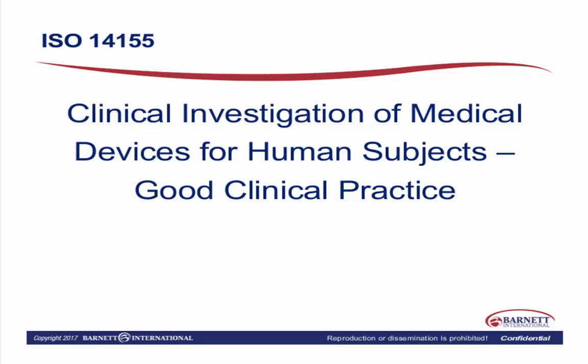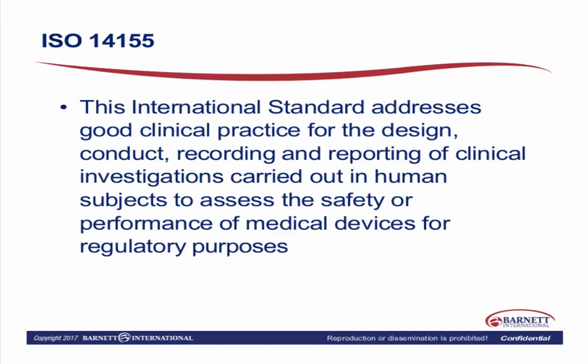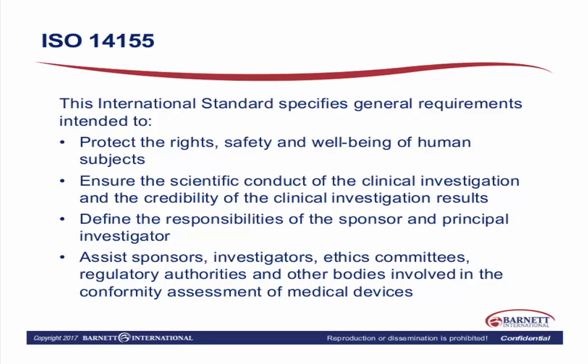The title of ISO 14155 is 'Clinical Investigation of Medical Devices for Human Subjects — Good Clinical Practice.' It outlines responsibilities for designing, conducting, recording, and reporting clinical investigations carried out in a human population to assess the safety or performance of medical devices for regulatory purposes. Some of the wording is very similar to what we see in ICH E6 GCP, which is written for pharmaceuticals — both seek scientific and ethical standards for engaging human subjects in studying investigational products.